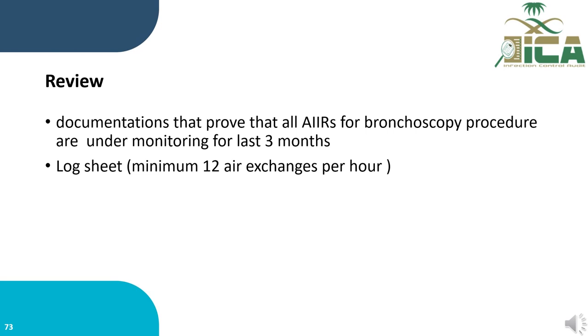And also you need to review the log sheet displaying monitoring of air change per hour, where a minimum of 12 air changes per hour is required, and also that air is exhausted outside 100% through a high efficiency particulate filter, and also the exhaust air duct is independent of the building exhaust air system.